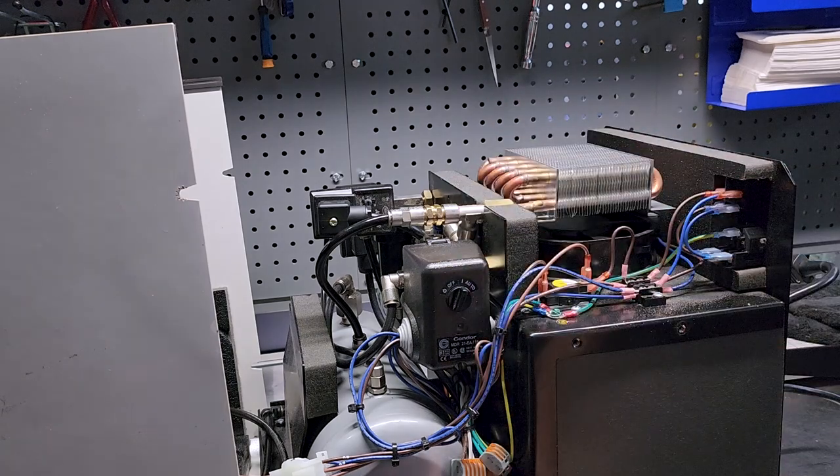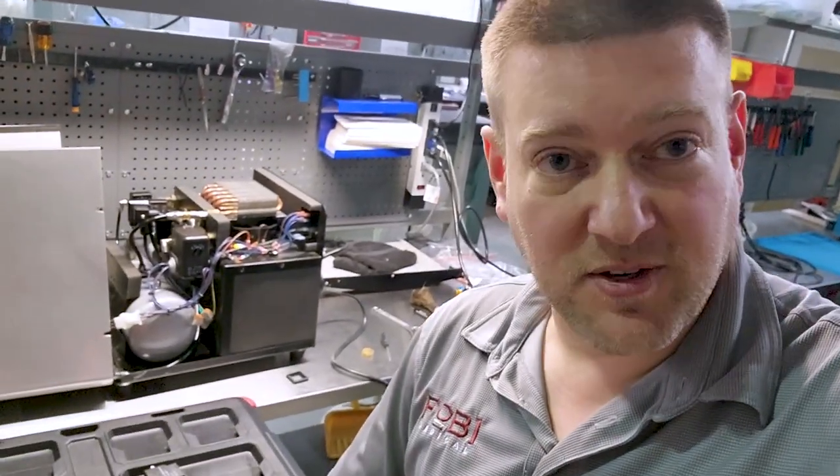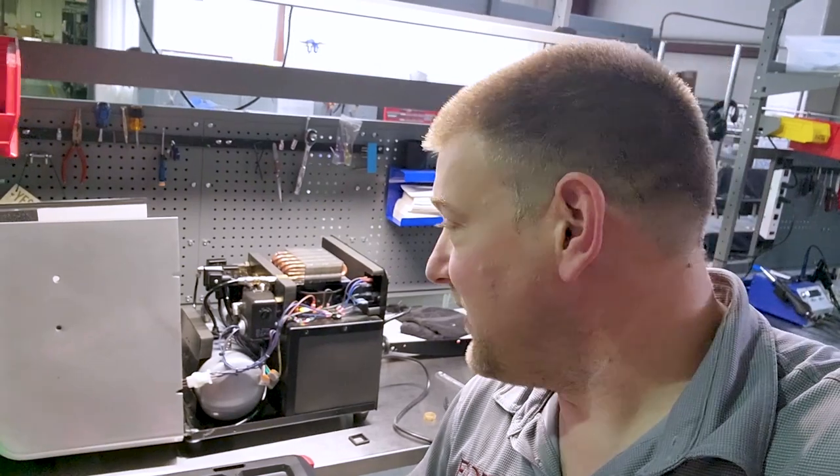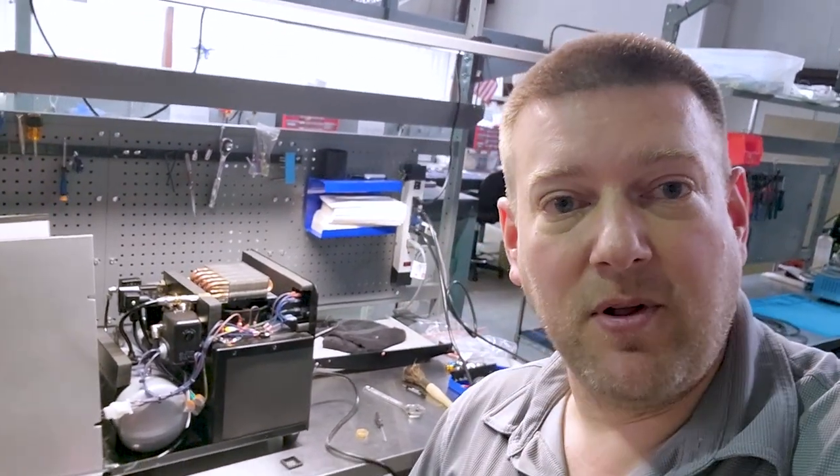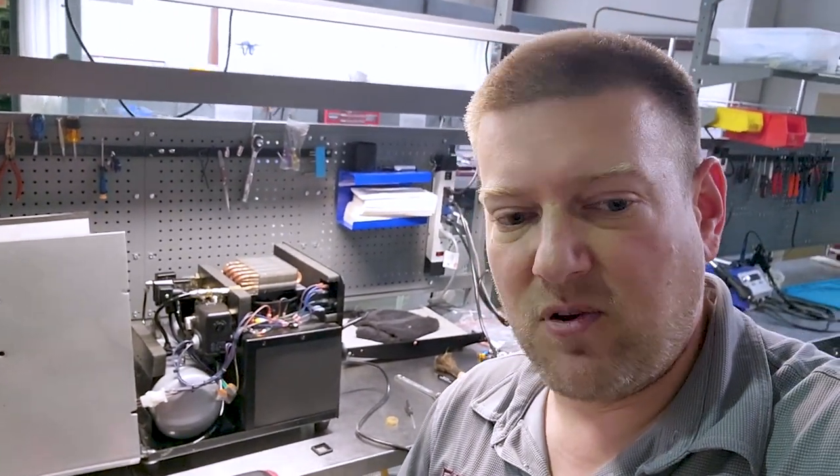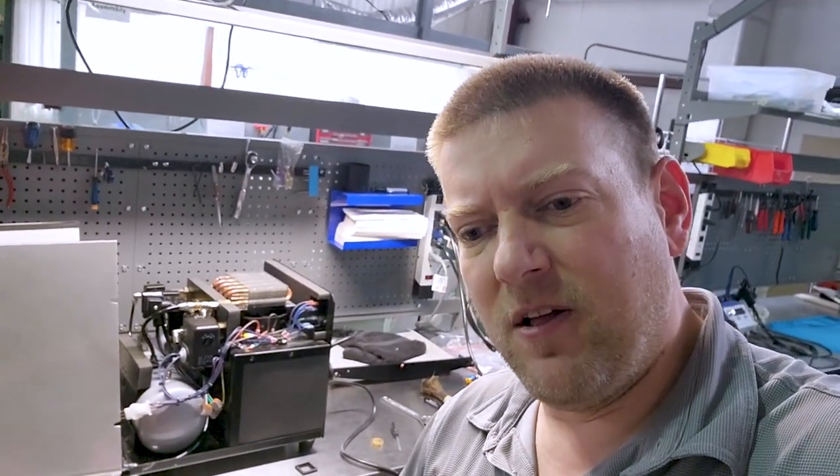It is electrically arcing mains to ground, which is technically very unsafe. So this is one of those situations where if the ground plug was broken and we were in here touching anything, even the edge of the case right here, I would be getting absolutely lit because it is arcing mains, which this guy operates on mains. You can see right here, voltage 115 volts. So it's arcing mains over to chassis, which is ground. And that is the arcy spark sound that you hear. So when you energize a coil and when you de-energize a coil is when there's two voltage spikes internally. And those voltage spikes have broken through the insulation. You can kind of see it inside the body right there. You can see the dark spots where it's arcing away to ground. Anyway, guys, I've never seen a problem like that before. It's interesting. It's a simple fix, really. It doesn't really require very much and the parts should be readily available.